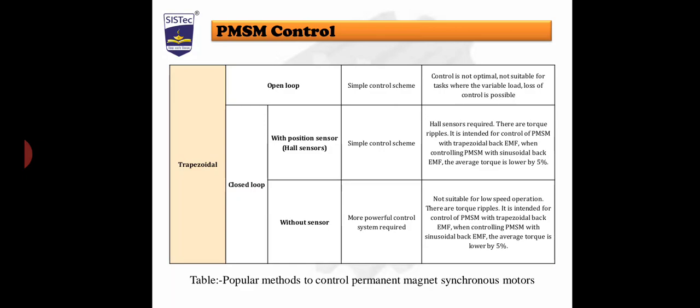For trapezoidal control without a sensor, a more powerful control system is required. The drawback is that this scheme is not suitable for lower speed operation. There is also torque ripple, and it is intended for the control of permanent magnet synchronous motors with trapezoidal back EMF. When controlling a permanent magnet synchronous machine with sinusoidal back EMF, the average torque is lower by five percent.